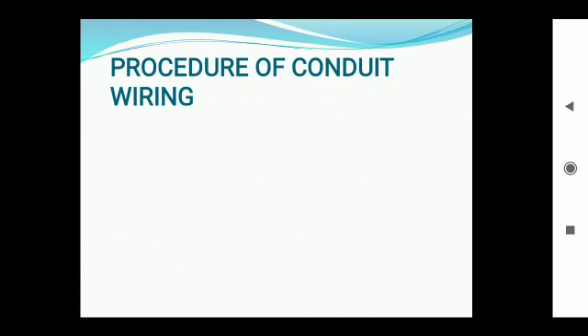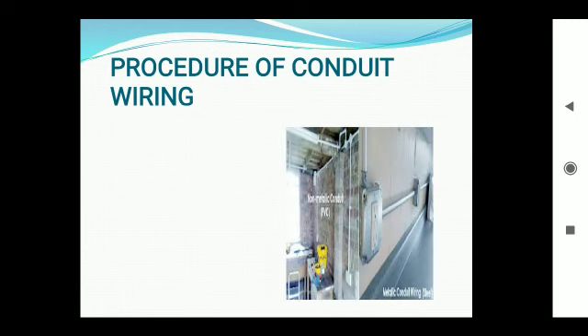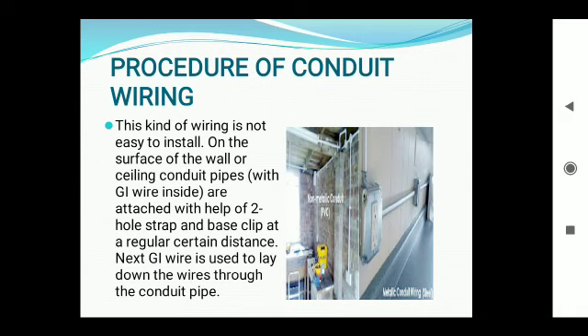Now the procedure of conduit wiring. You can see there is an image of metallic conduit wiring as well as non-metallic conduit wiring. That means a steel conduit and PVC conduit. This kind of wiring is not easy to install on the surface of the wall or ceiling. Conduit pipes are attached with the help of two-hole strap and base clip at a regular distance. And next, GI wire is used to lay down the wires through the conduit pipe, and GI wire is also used for earthing purpose.